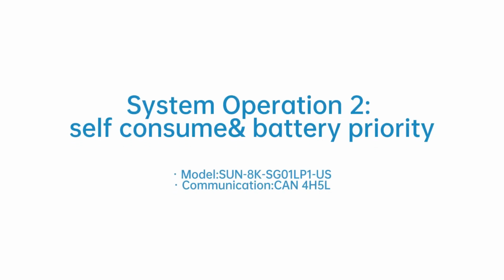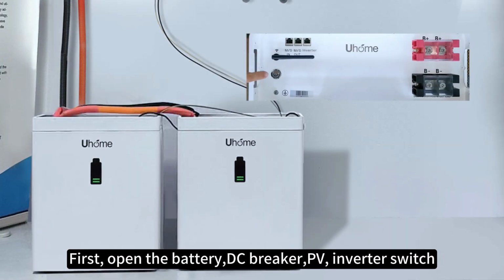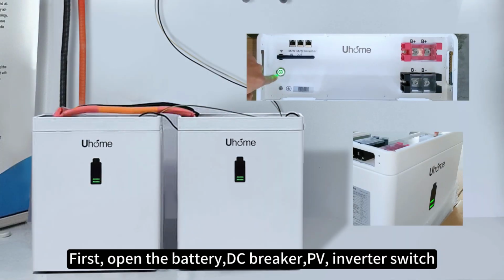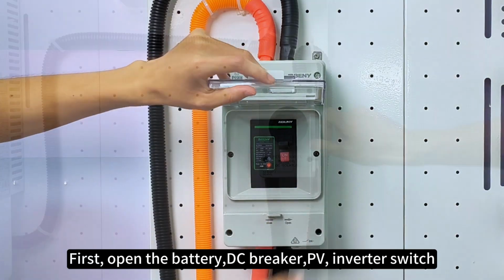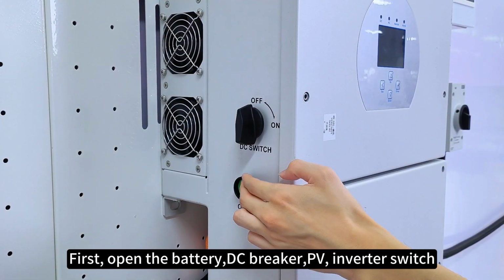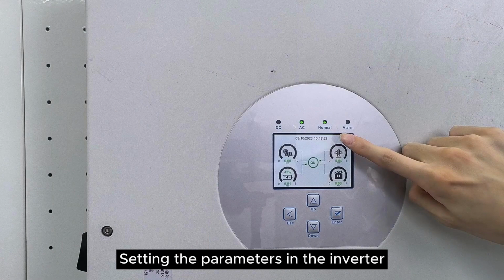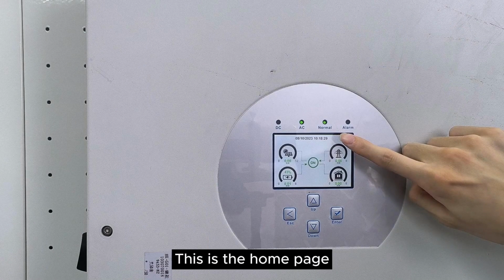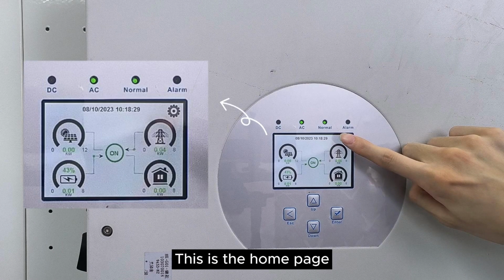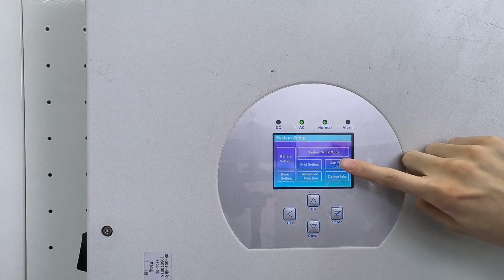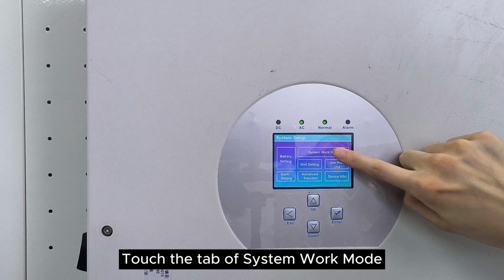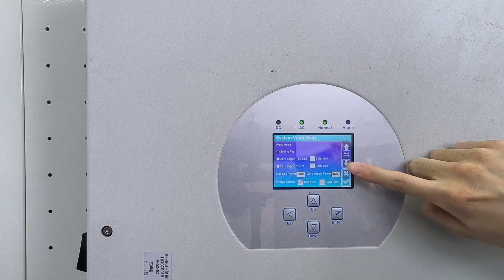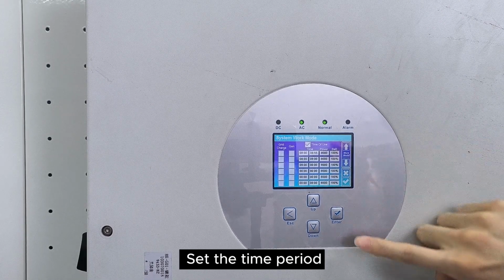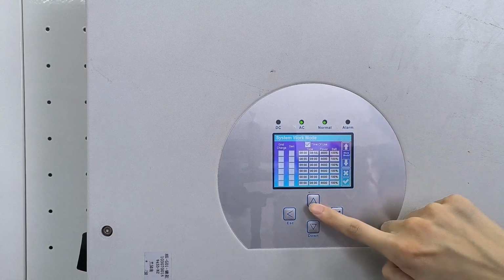System Operation 2, Self-Consume and Battery Priority. First, open the battery, DC breaker, PV, inverter switch. Setting the parameters in the inverter. This is the home page. Select Settings. Touch the tab of System Work Mode. Set the time period.